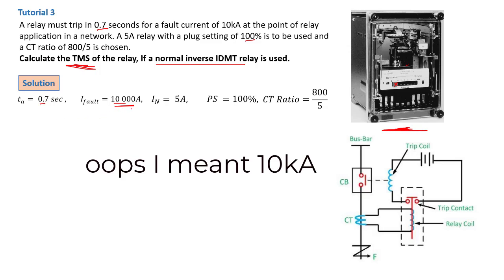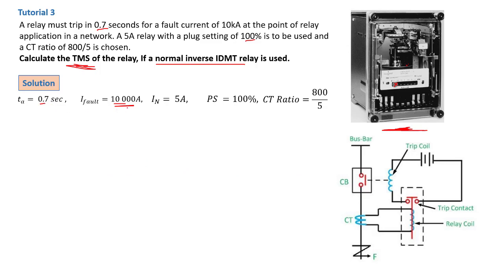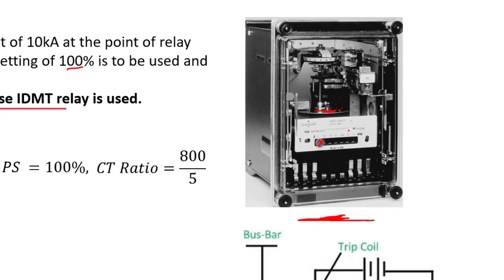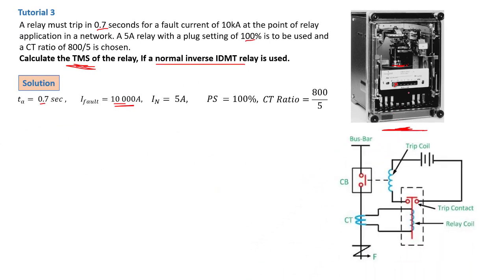If the fault current is reduced — say to 1,000 amps — the relay timing increases; it may be 5 seconds instead of 0.7 seconds. The higher the fault current, the faster the disc turns, as you can see on screen. The speed of the disc determines how fast it reaches the tripping point, and that depends on how much the coil is energized. If the fault is higher, the coil is more energized, the disc speeds up, and the relay trips faster — and vice versa.